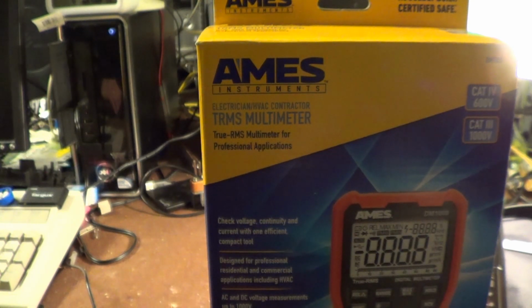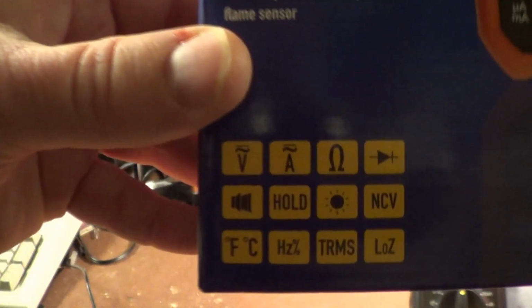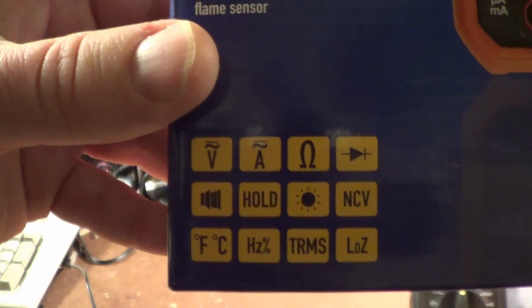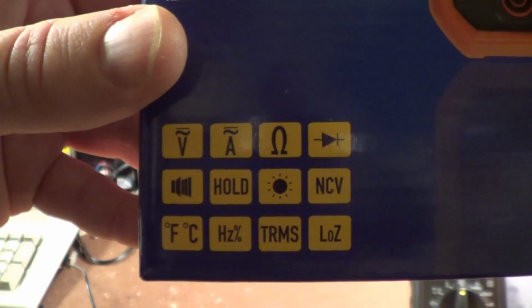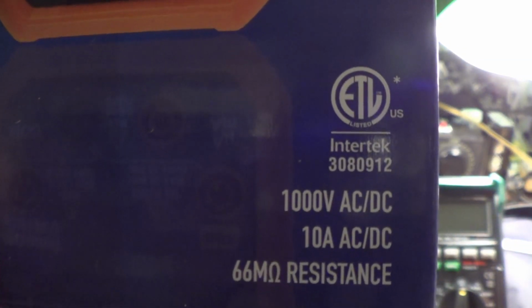And that's exactly what the low Z measurement setting does. It greatly reduces the multimeter's input resistance or impedance figure, usually from 10 megaohms down to about 3k ohms, in the hopes of loading down an induced voltage so that you'll see it's not really there. Down at the lower left-hand corner of the package, you can see a series of icons indicating all the major test ranges. There's the ETL Intertek badge and a number.